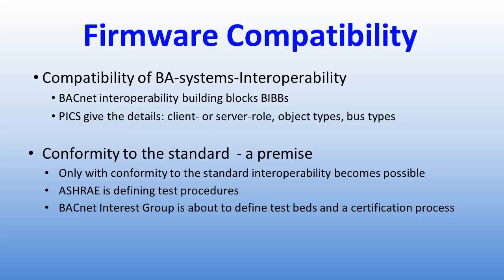Some examples of what would be contained in the PICS are: basic information identifying the vendor and describing the BACnet device, the BIBs supported by the device, the standard BACnet device profile, all non-standard application services that are supported, a list of all standard and proprietary object types that are supported, any optional properties that are supported, which properties can be written using BACnet services, whether objects can be created or deleted using BACnet services, and any restrictions on the range of values for them.